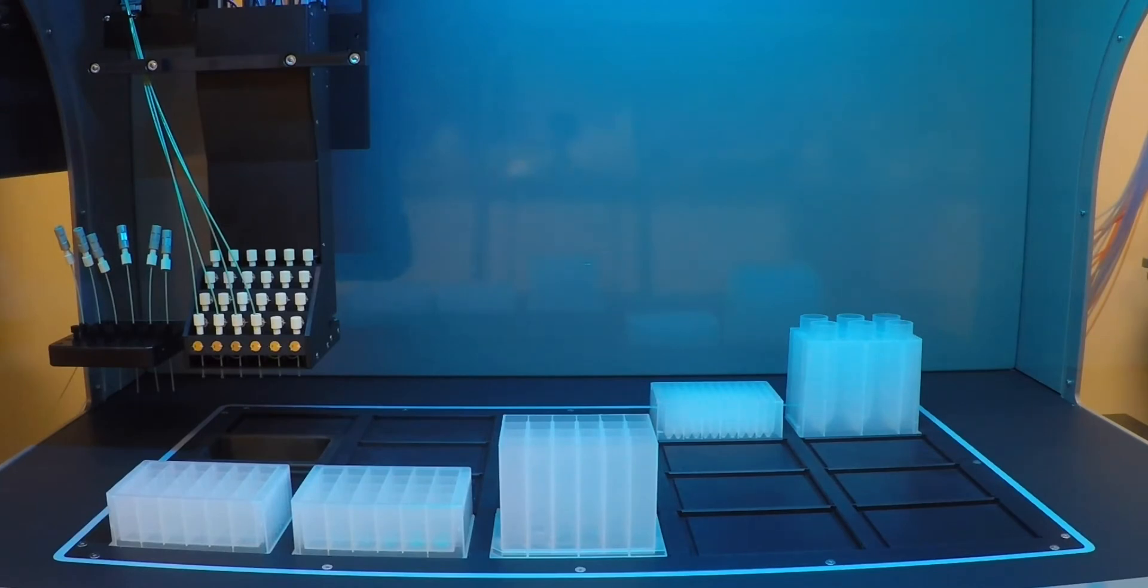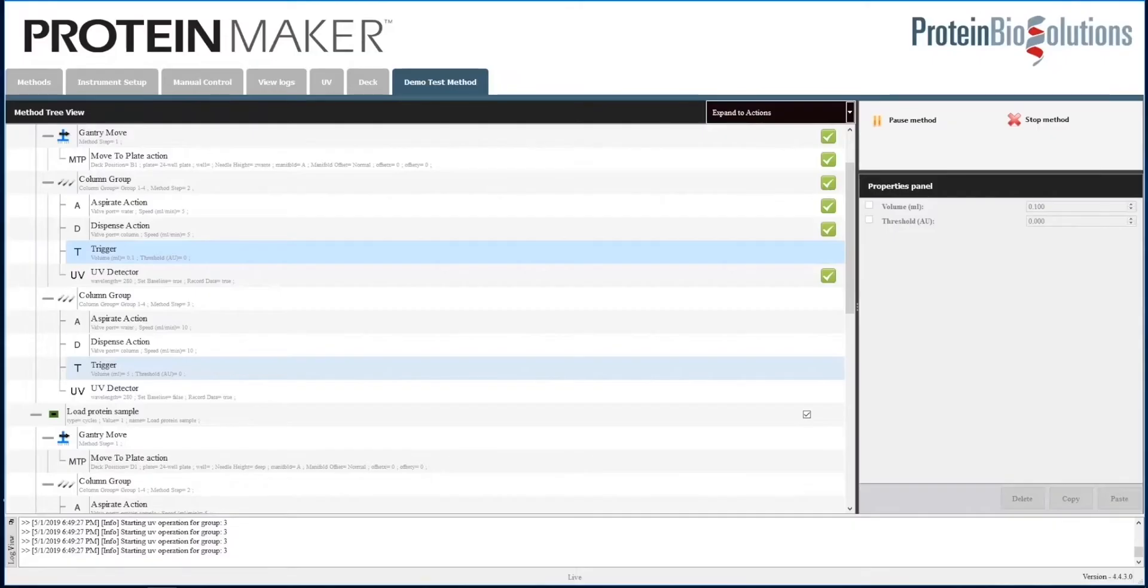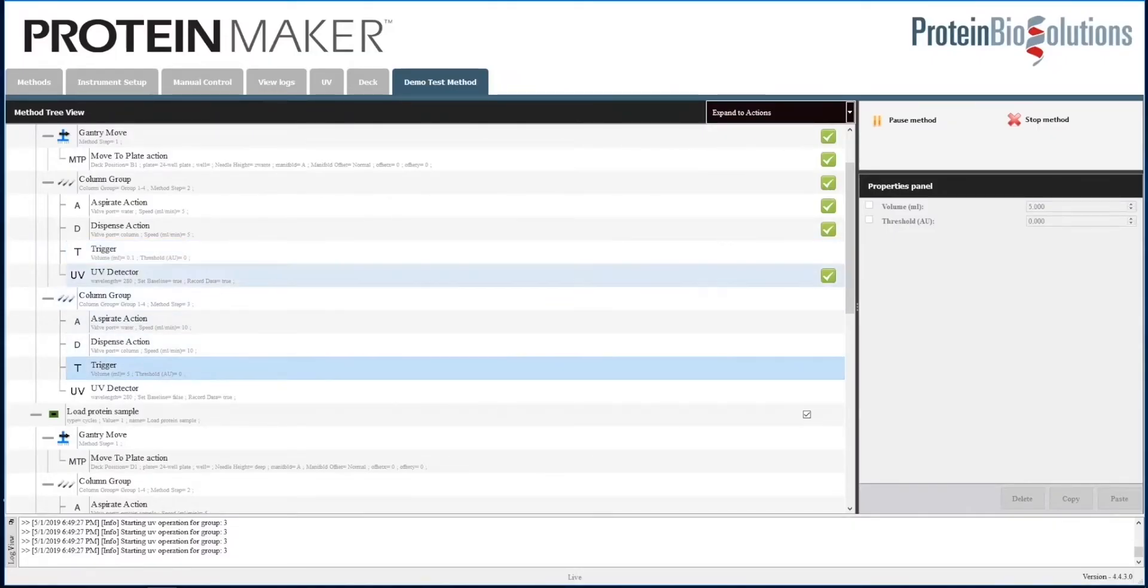In this case we are using the waste position, where the robotic arm just moved, and we are using the front three positions which are holding these three 24-well plates, two shorter and one taller. The software operates by grouping channels together, as we've already discussed, and then giving a command to that group.